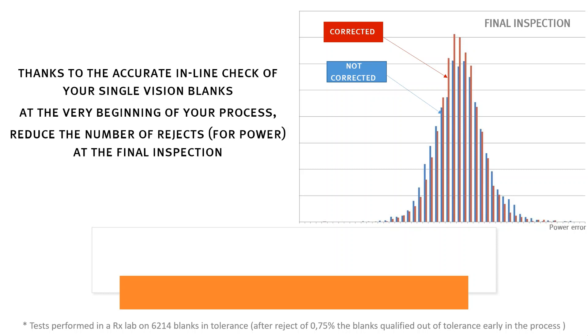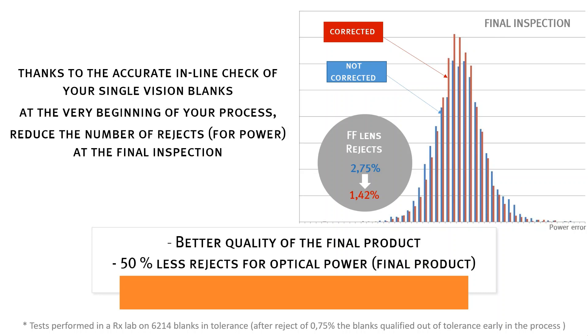Simply, the lab is producing more lenses within tolerance. Analysis of this data shows that when applying the ISO standard, the lab's baseline of rejects for power is around 3%. However, by adding compensation, the reject rate is reduced to 1.5%, which is a 50% reduction.